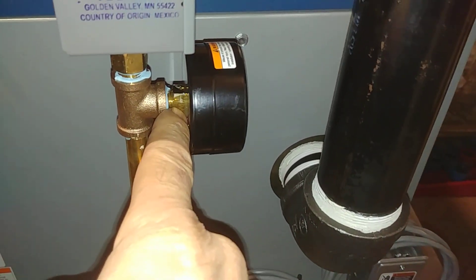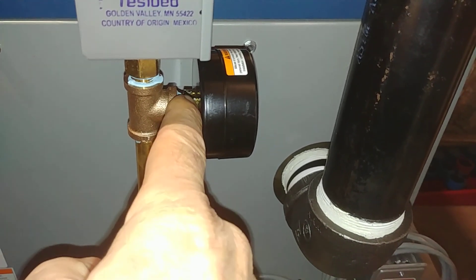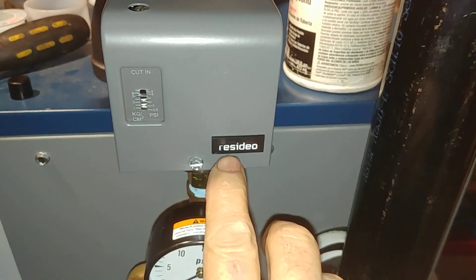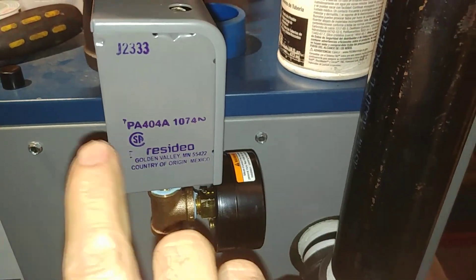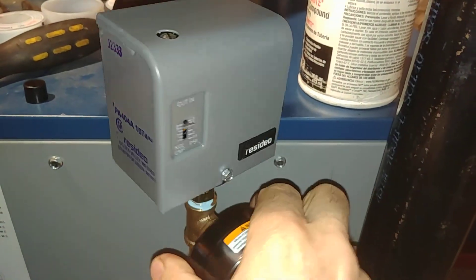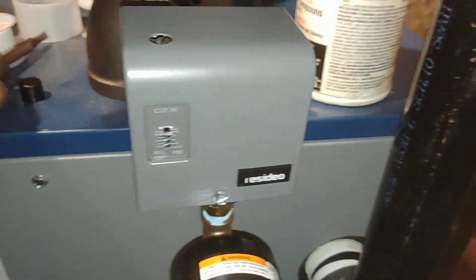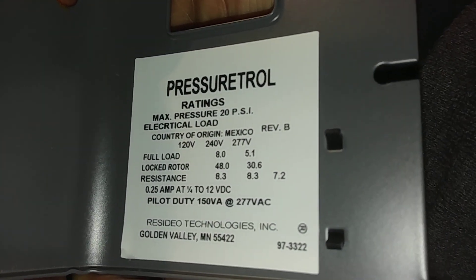Sometimes the pigtail gets clogged and you've got to get an open-end 14 millimeter wrench, or 9/16 inch wrench sometimes. We're going to be getting back to this pressure trol here — it says Resideo, which is Honeywell's new name. We're looking at the PA 404A 1074, and there's the date code. What you want to do is remove — or back out — this screw with a quarter-inch nut. There's the cover and there's the rating.